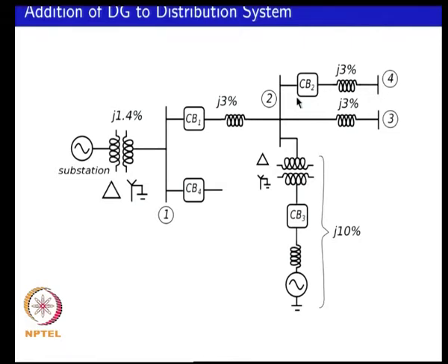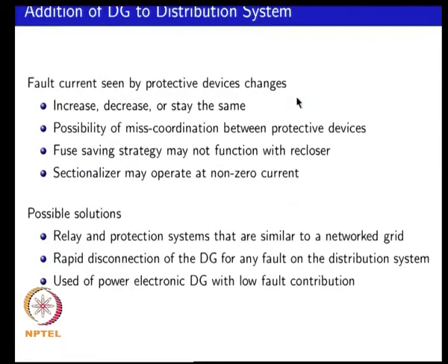You also have the situation where, because of the change in current level, a recloser whose coordination settings might have been done to obtain a fuse saving strategy — because of the change in current levels with the addition of DG — the fuse saving strategy may no longer work. So now there is a direct cost impact on the utility because of the addition of the DG source.